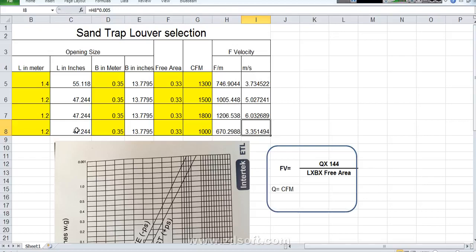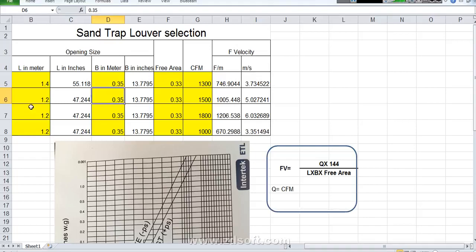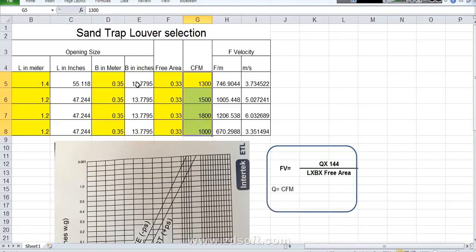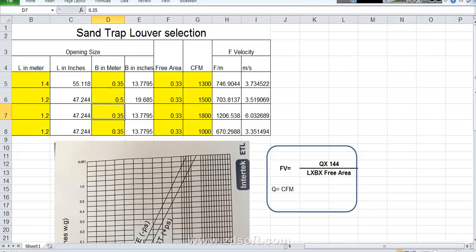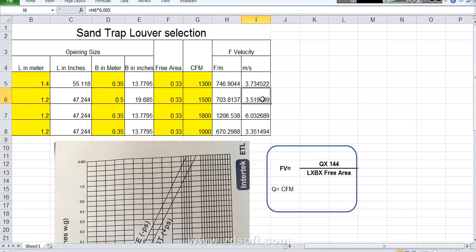So in this case for this duct, this size of the louver. For example 1.2 into 0.35 and the CFM is 1500. The CFM we cannot change. Free area we cannot change because it is manufacturer. So again next point we need to change our sand trap louver size. The opening size and louver size we can change. Here we will change the value now. Because I am increasing the height of the sand trap louver, 0.5 meter I will put. So automatically see here this face velocity is decreased.